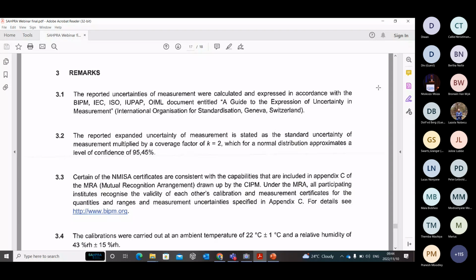As you can see, as I mentioned, the 95% confidence, we also mentioned the environmental conditions at which the instrument was calibrated. In this case, it is 22 degrees, with an uncertainty as well. As I mentioned, no measurement is complete without uncertainty. We have 22 degrees, but we allow an uncertainty of one degree. This means that in our lab, in each and every hour, we cannot let the temperature increase or decrease by more than 1 degree. And also, we look at the humidity conditions, in this case 43%, at an uncertainty of 15%.